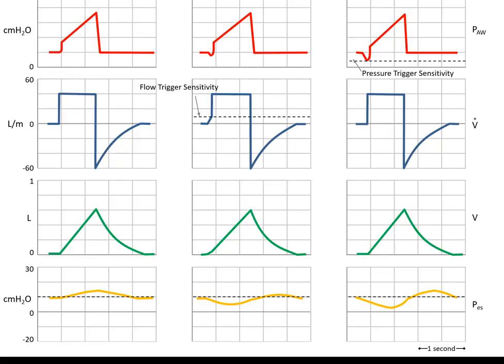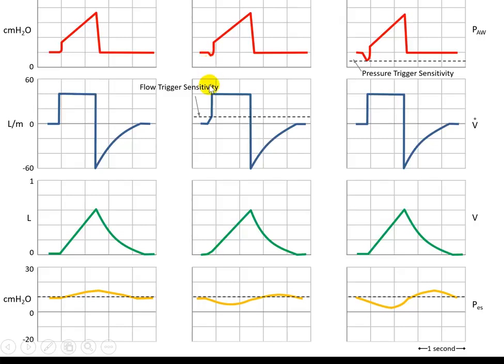The second thing we need to understand is the phase variables, which are specific to the delivered breaths. Each breath needs to be initiated by a trigger. That trigger could be time if the breath is mandatory or controlled — meaning the patient is making no efforts at all. That's why you don't see any negative deflection in the pressure or an increase in flow. The breath started after a set time has elapsed, so the trigger here is time.